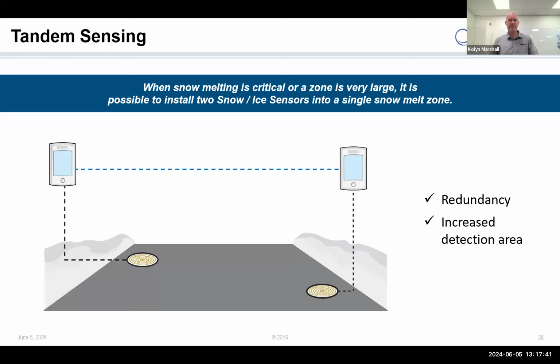It can impact temperatures of sidewalks versus parking lots. It can impact drifting of snow. It can impact a lot of factors. So sensor placement is critical on knowing the performance and responsivity of the system as a whole. Having multiple sensors can allow me to maybe make adjustments based on how the environment impacts the performance.